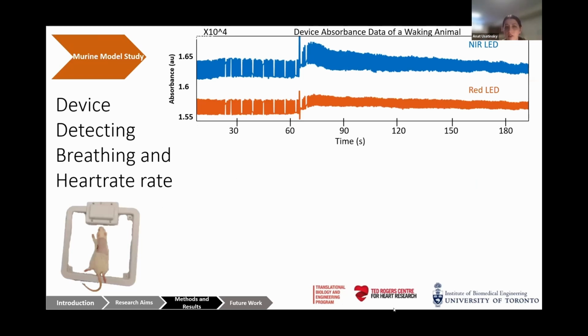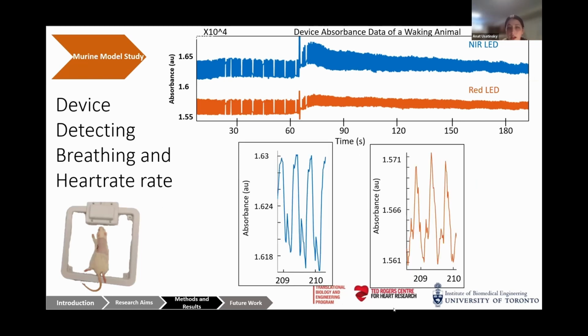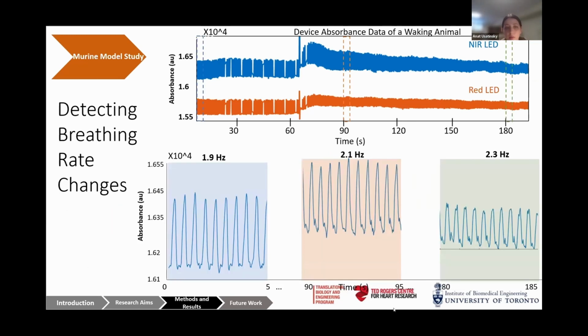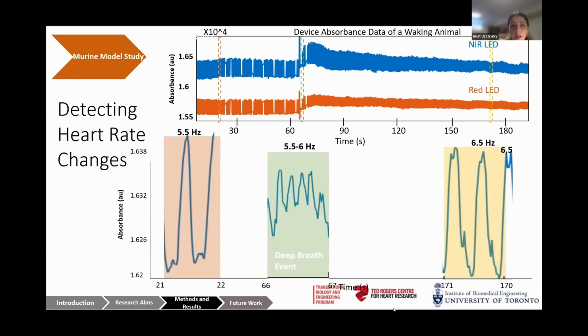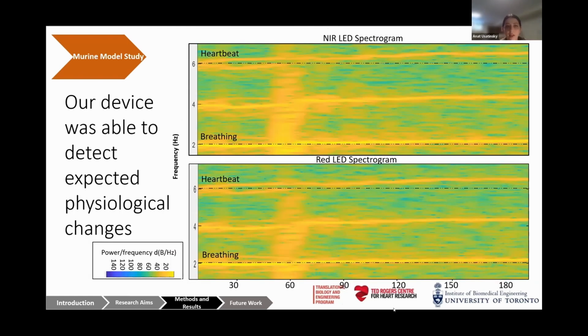When we came in for a functionality test, this is just one data set of an animal as it's waking up from isoflurane. We were able to see that we can actually detect both breathing artifacts and heart rate. We were also capable of seeing that our device is able to pick up on small frequency changes, such as here in the breathing rate as the animal wakes up, and in the heart rate as the animal wakes up from isoflurane. In a slightly different perspective, this is a spectrogram, which essentially plots the frequency over time. And we do see the frequency of heartbeat and breathing increases over time. And this is an expected physiological phenomenon that occurs as an animal wakes up from isoflurane.